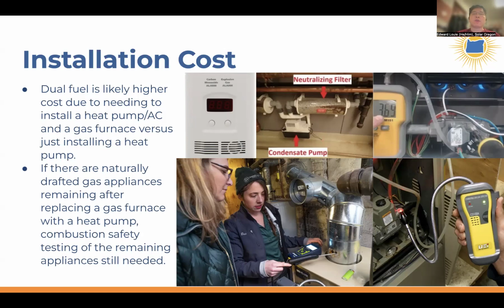A very efficient gas furnace, like a 95, 96, 97% efficient gas furnace, produces condensate, and that condensate is a little bit acidic, and so you need an acid neutralizing filter in order to protect the sewer pipe or the condensate pump from being corroded by this slightly acidic condensate. So that's a cost, and also it's an ongoing maintenance to restock that neutralizing filter material.